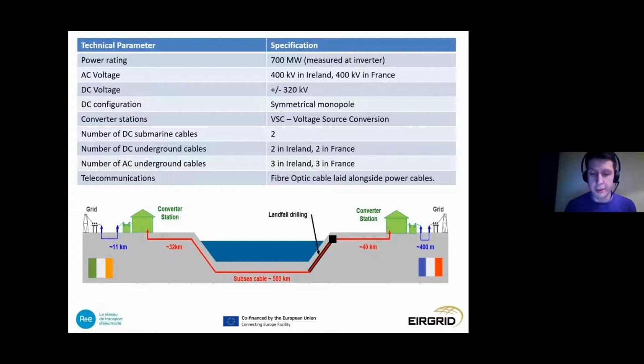VSC schemes can also provide good advantages or required characteristics, let's say, to optimize the benefits for Ireland and France. We can get voltage support for the regions, we can provide black start capability, and we can provide frequency response to faults on both systems. The VSC technology that's been chosen will be in what's known as a single terminal symmetrical monopole configuration. We're also looking at laying fiber optic cable alongside the power cable, and this would be primarily to provide communication between the two converter stations in Ireland and France, with potential for further communication also.